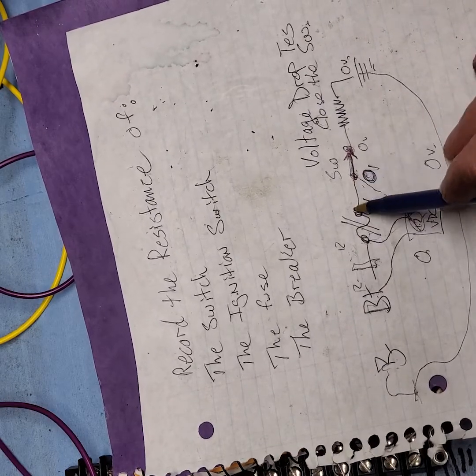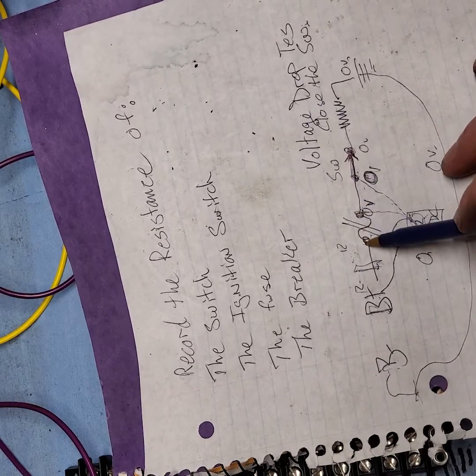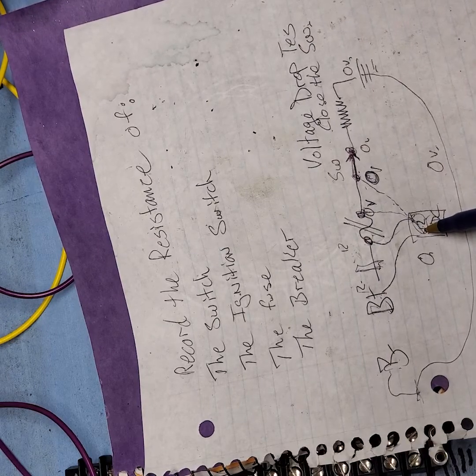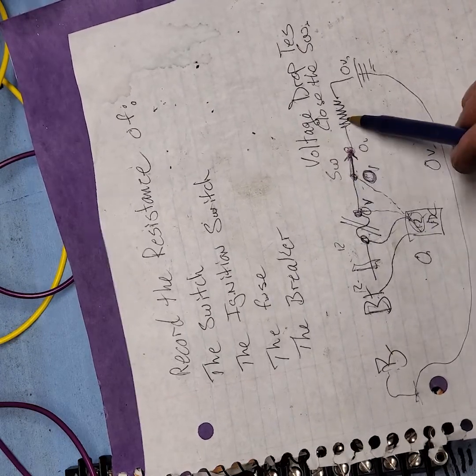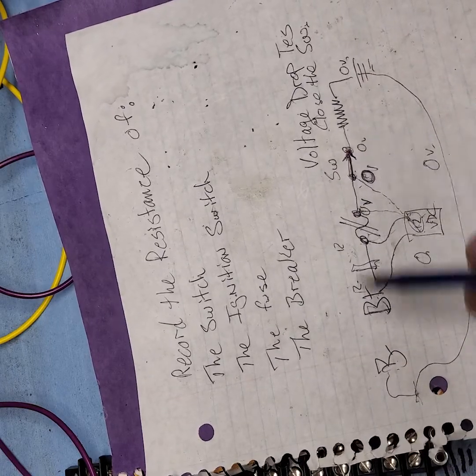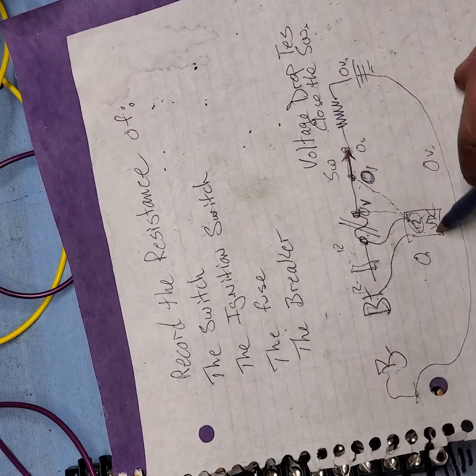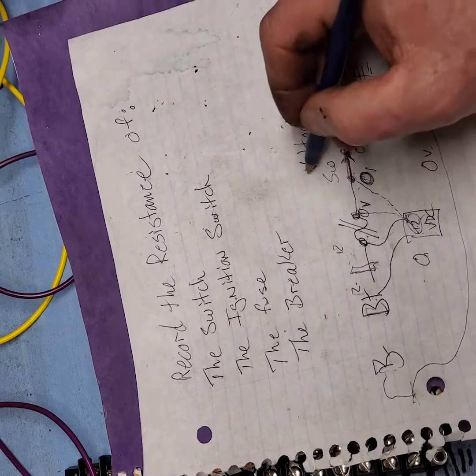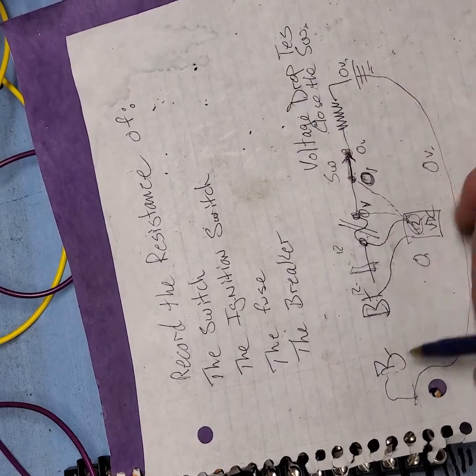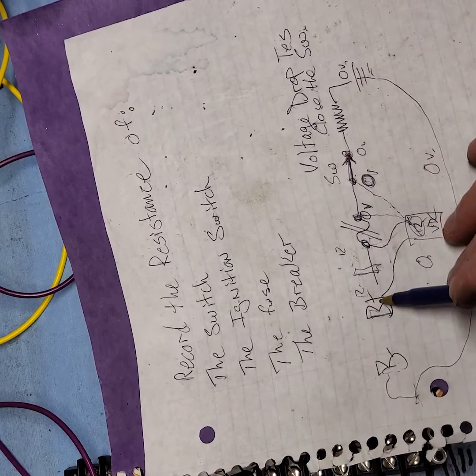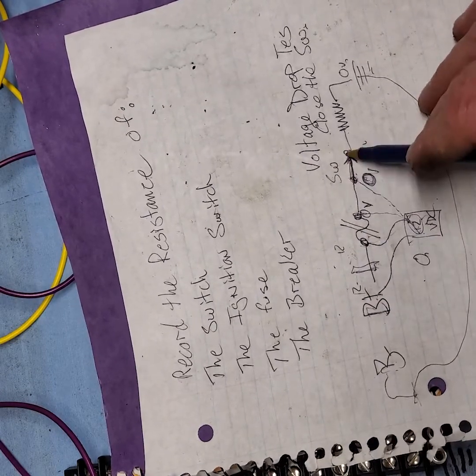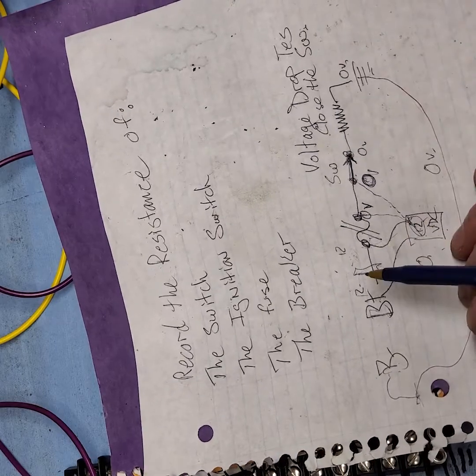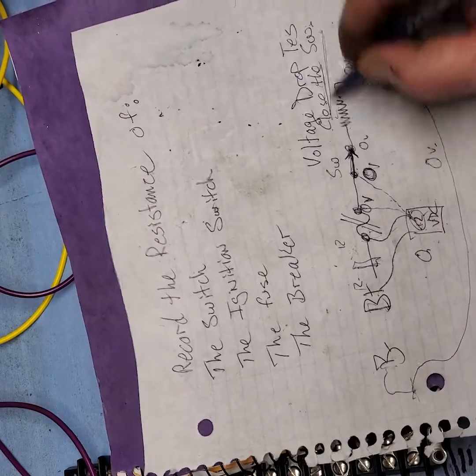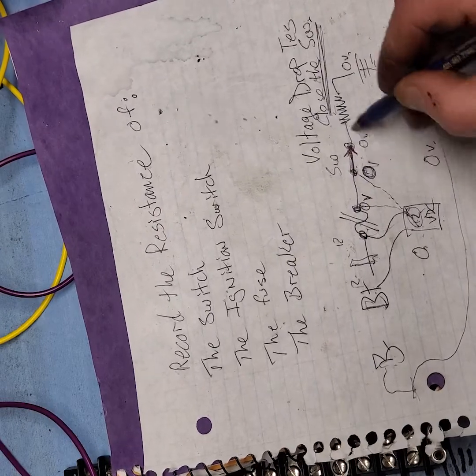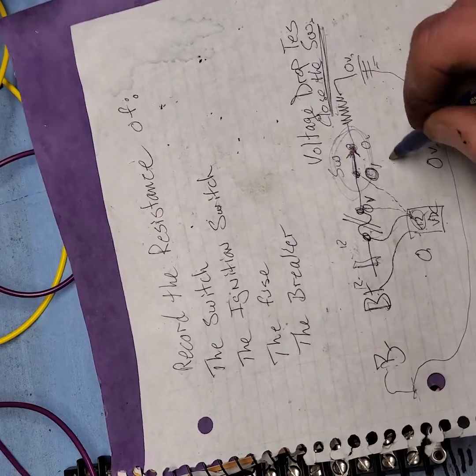If I start to back up, as soon as I get to where I have power, my meter would read power. That's another way to do it. That's ground minus ground. 0 minus 0 is 0. It works the same way. So the big thing to remember in a voltage drop test is, here's the secret. This is the secret part. You can remember to take it on power and go to power and go to power, and the meter reads nothing. Nothing happens. What you have to do is you have to close that switch. Remember, energize that circuit. That's the secret. If you don't energize the circuit, nothing happens.